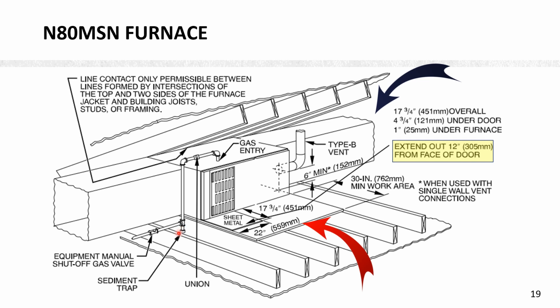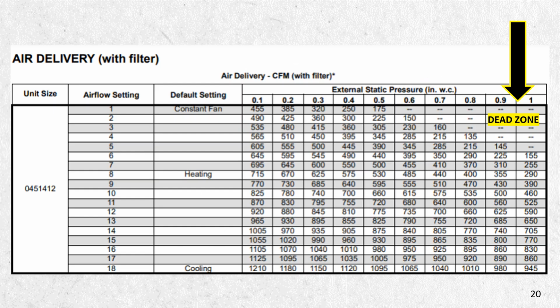You also have a sediment trap here on your gas line. And then one thing I've seen, and we'll look at some of this, is some of the northern regions will put a sediment trap right here too on your flue. So as the blower motor stops and the flue starts to come back down, the liquid comes through here and it would just drop in the bottom instead of running back into your furnace.